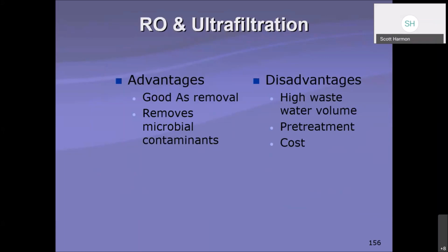the percentage of loss can be anywhere from 5 to 30%. They may be better these days than when I've operated membranes in the past, but you're still losing a lot of your flow. You have to have pre-treatment in certain situations with these membranes because there's certain things that you can't put into the membranes themselves.